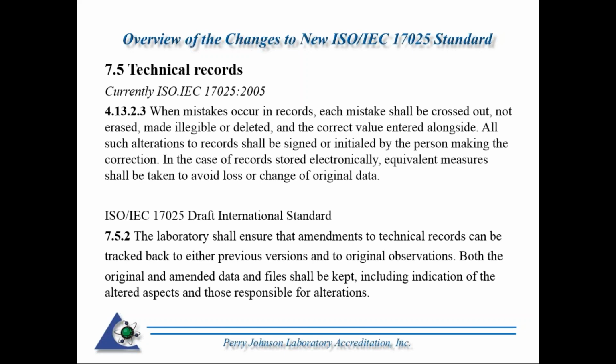Under the new draft international standard, the laboratory shall ensure that amendments to technical records can be tracked back to the previous version and to the original observation. Both the original and amended data and files shall be kept, including indication of the altered aspect and those responsible for alterations. So not so prescriptive there. It's up to the lab to determine how it's going to comply.